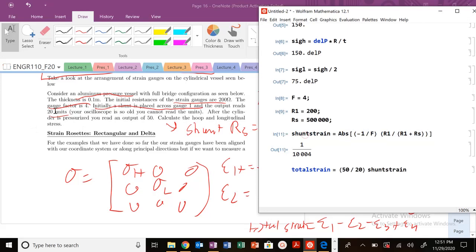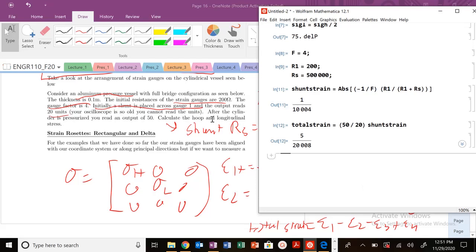Because again, at this strain, when we close the switch, we were at an output of 20. Once we pressurize, we were at an output of 50. So that new strain, the strain that's induced once we pressurize that pressure vessel, that is going to be this strain right here. So that is going to be my total strain.